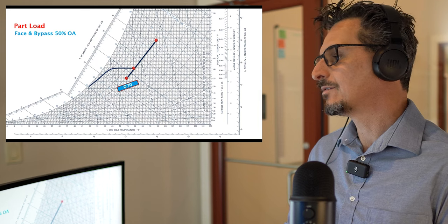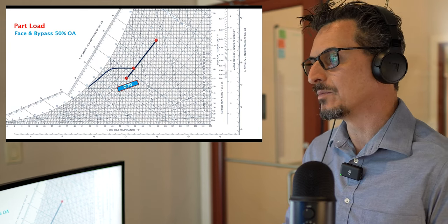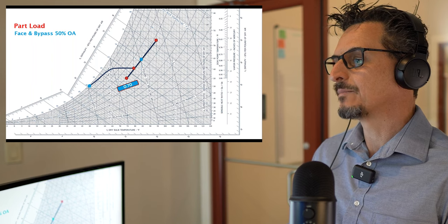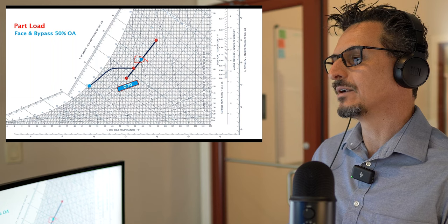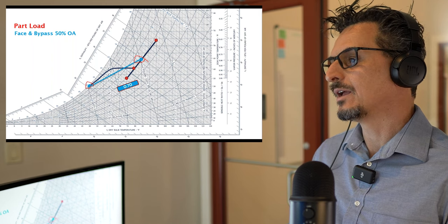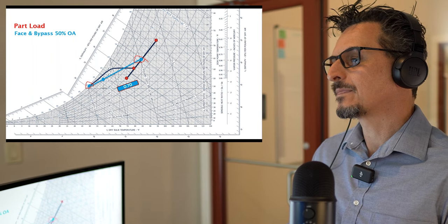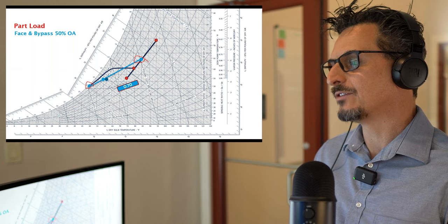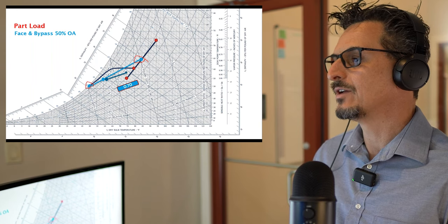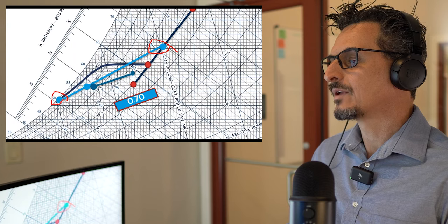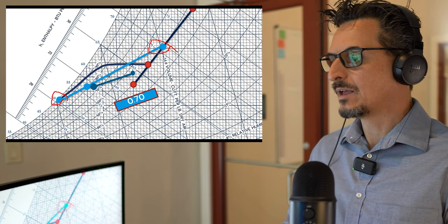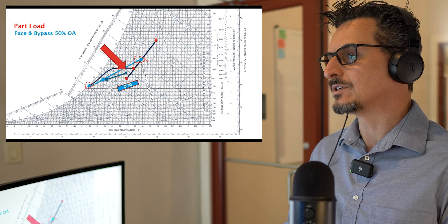Where face and bypass can fail is if you have a lot of outdoor air — say 50% OA. The bypass air is at the higher humidity mixed air temperature, and when it mixes with the 51°F coil-leaving air, you end up at a higher supply humidity. Drawing the 0.7 SHR line, you'd be at about 58% RH — better than no face and bypass, but still somewhat elevated. Whether that's a problem depends on design intent, what the owner expects, and the type of facility.